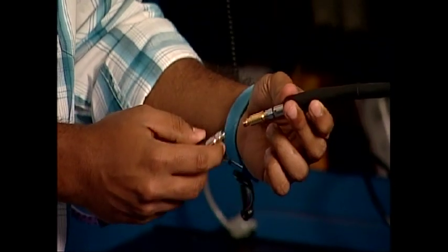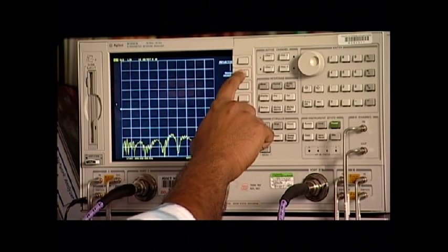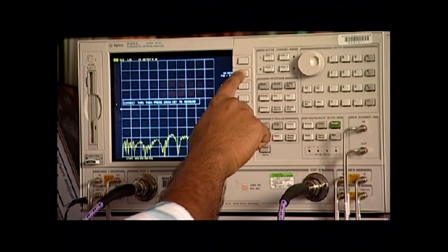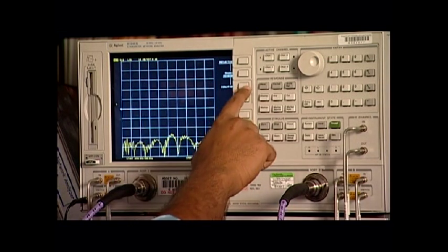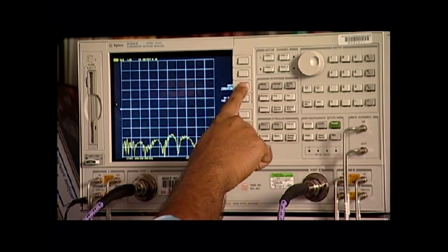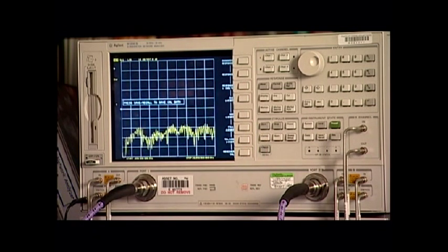For the transmission measurements, we connect the through between the ports 1 and 2. We then select transmission, do both forward and reverse. Since we're omitting the isolation part, we select isolation, omit isolation, done 2 port calibration.